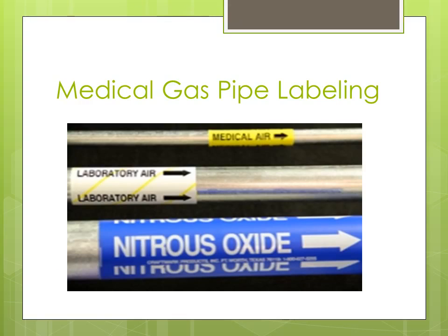A couple more slides that I wanted to put in here as I did this presentation are on medical gas pipe labeling. Again, this is one of those areas where I don't believe the accreditation agencies have scrutinized organizations as closely as they could. In all the surveys I've been to, I have yet to have a surveyor actually take NFPA 99, apply that code, and concentrate on medical gas pipe labeling. It is very specific, and I'm going to go over a couple of things on the next slide.